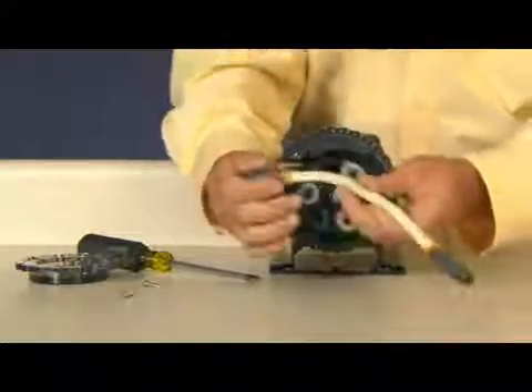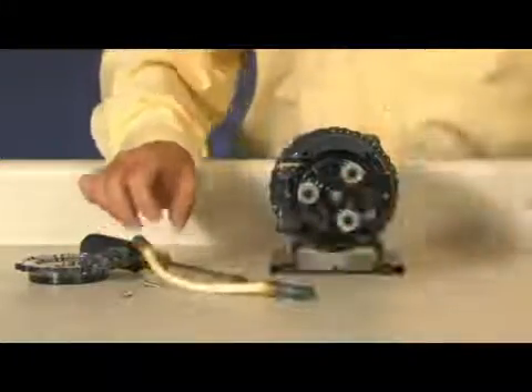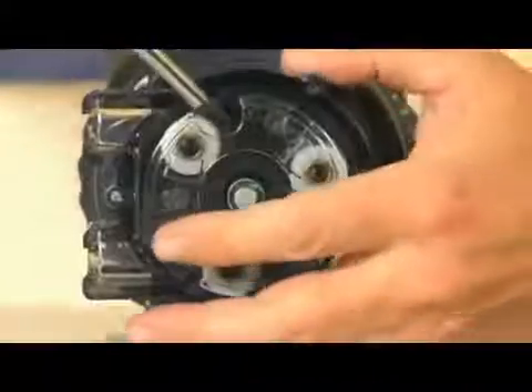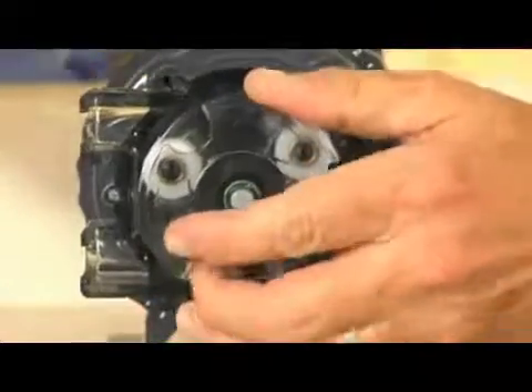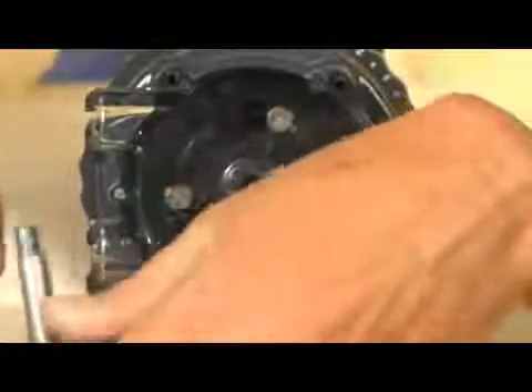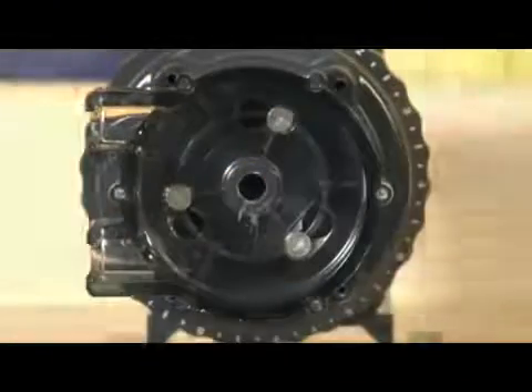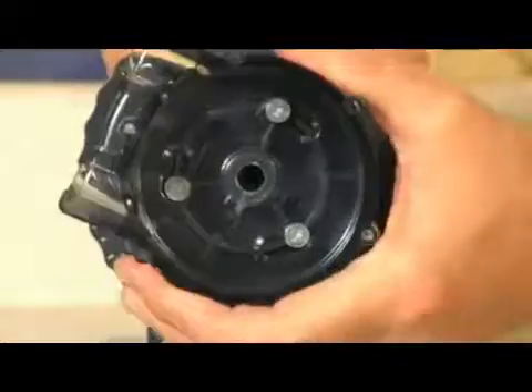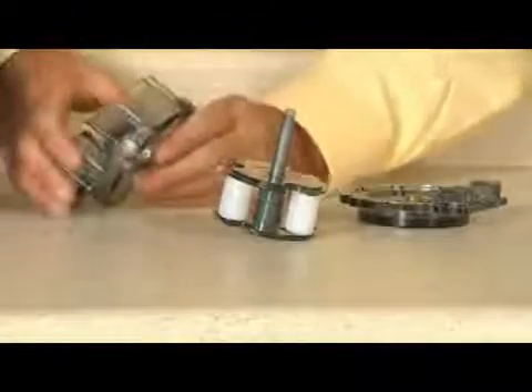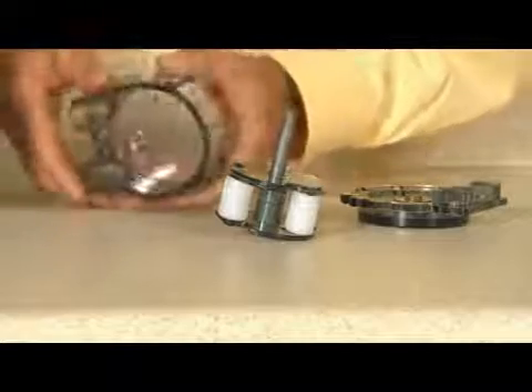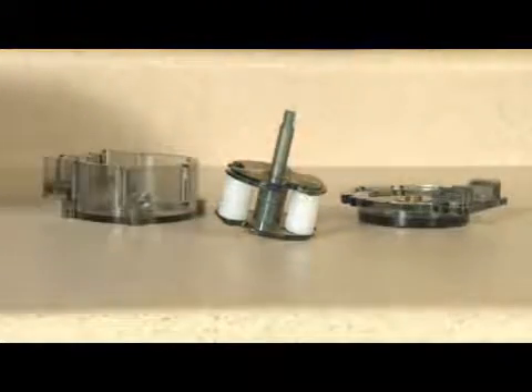Turn the pump off. Remove and discard the pump tube. Remove the roller assembly, shaft, and housing. Use a non-citrus all-purpose cleaner to clean chemical residue from the pump head housing, roller assembly, and cover. Check the housing for cracks. Replace if cracked. Ensure the rollers turn freely.